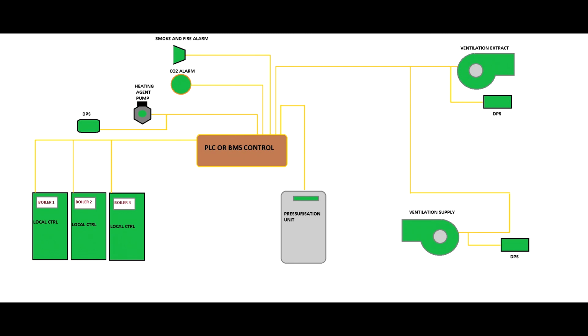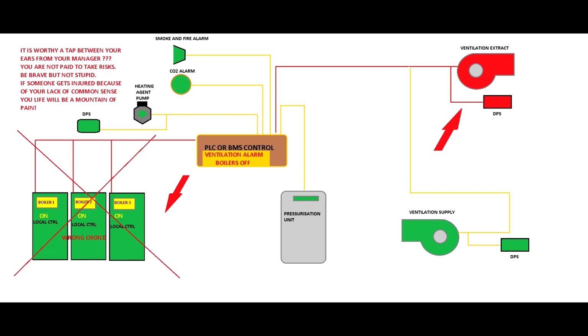So, coming back to my story, if the fan had been integrated directly with the boilers, he wouldn't have been able to turn the boiler on. But because it is integrated with the PLC and the PLC was used as a control and as a safety, the fan differential pressure switch, which sends a signal to the PLC, did not stop the boilers when the boiler local control was bypassed. And that was bad. Thank you very much, and I'll see you next time.